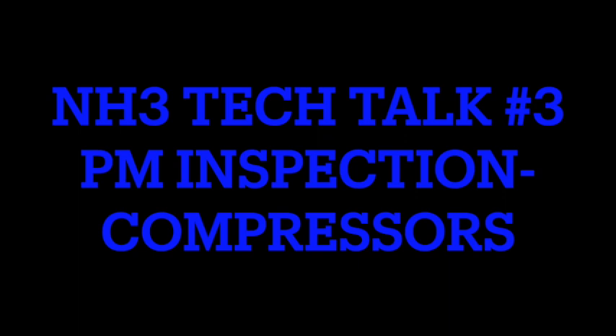So if you do start compressors, you need to have them in manual mode and unloaded, start them unloaded and let them run, checking whatever you can. Even starting up a compressor like that can pull down the suction pressure too far, which is very easy to do depending on the system and how big the compressors are. You might not be able to do that, you might have to turn one off and one on, and maybe the customer doesn't even want to do that today because last time they did, they messed up and production got shut down. So sometimes you can't run all the compressors, or sometimes you can't turn them off because they're all running.